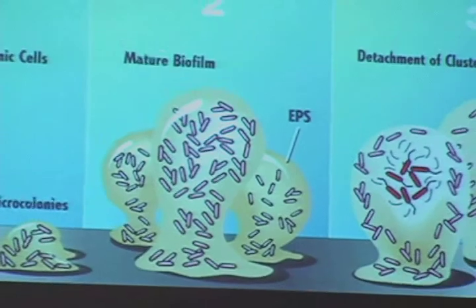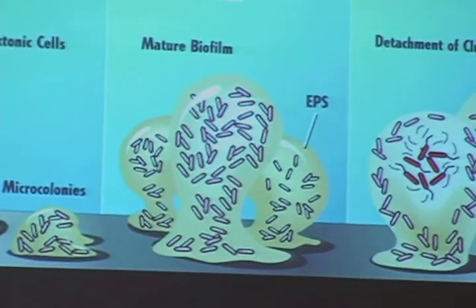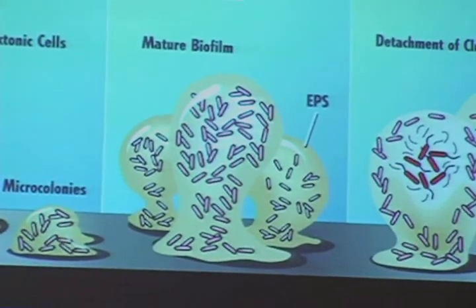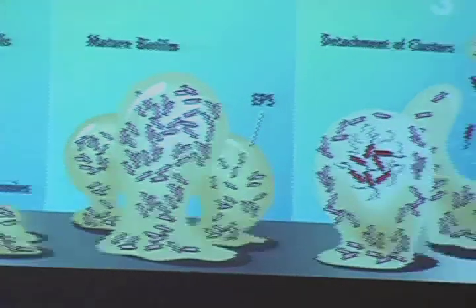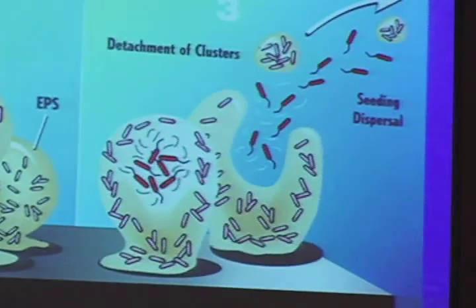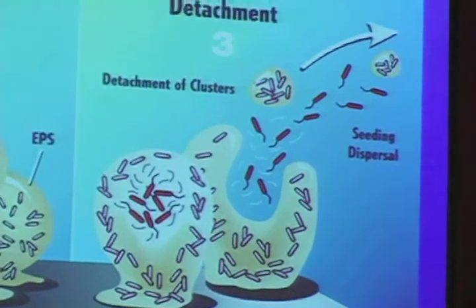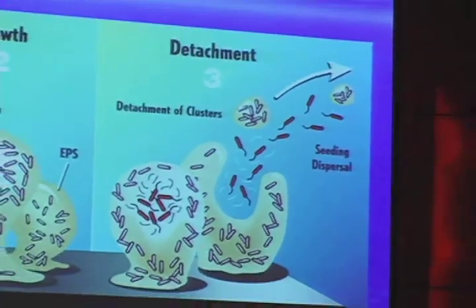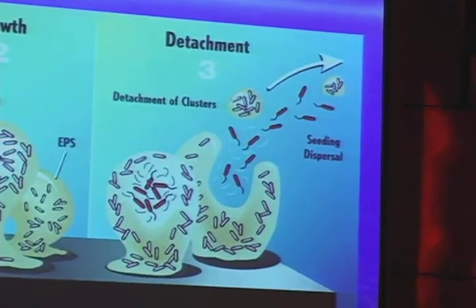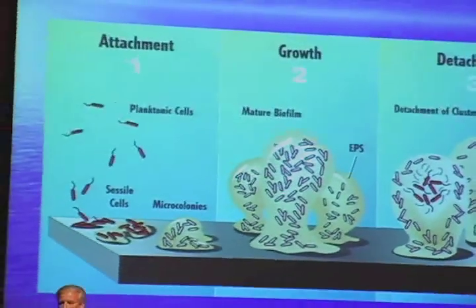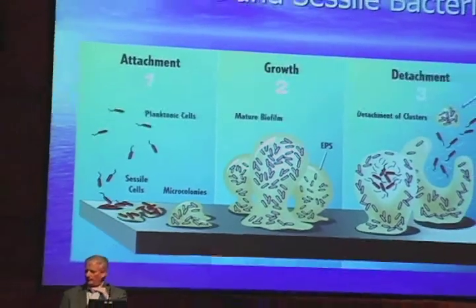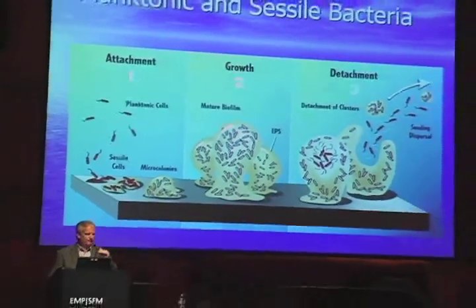It actually digs down into the metal surface and causes some very damaging pitting corrosion. This biofilm, because it grows at certain points and to certain heights, because of the flow, actually discharges and leaks itself back out into the system that goes around the tower, and it finds a way to establish residence somewhere else. So if you don't control both the biological activity in the bulk water, which is the planktonic cells, and find a way to have a program that controls it on the pipe surface level, then you might be missing the boat.